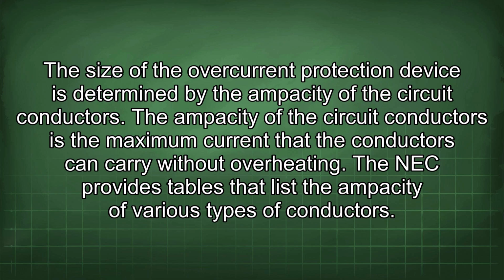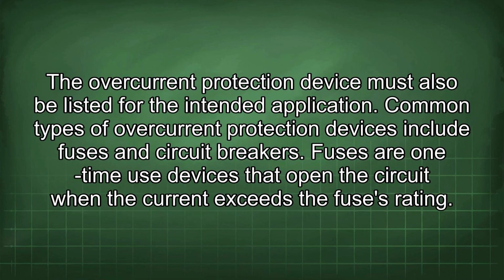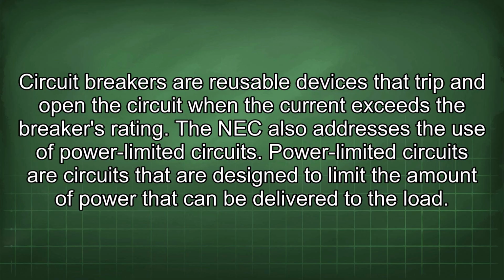The NEC provides tables that list the ampacity of various types of conductors. The overcurrent protection device must also be listed for the intended application. Common types of overcurrent protection devices include fuses and circuit breakers. Fuses are one-time use devices that open the circuit when the current exceeds the fuse's rating. Circuit breakers are reusable devices that trip and open the circuit when the current exceeds the breaker's rating.